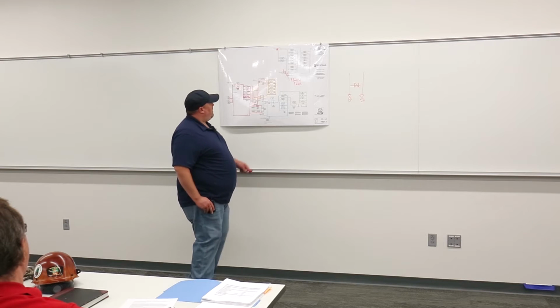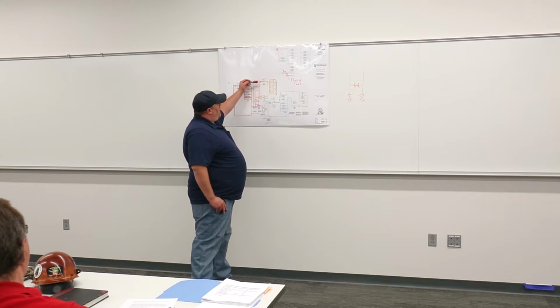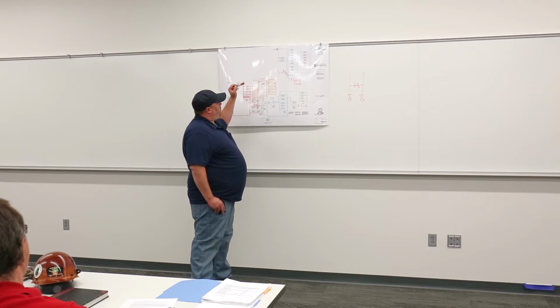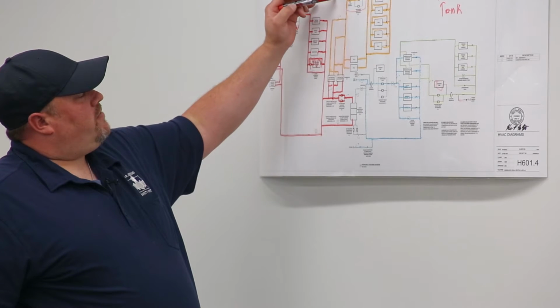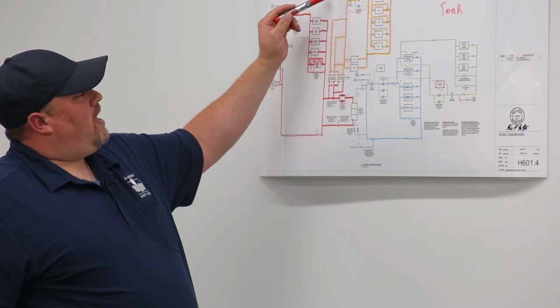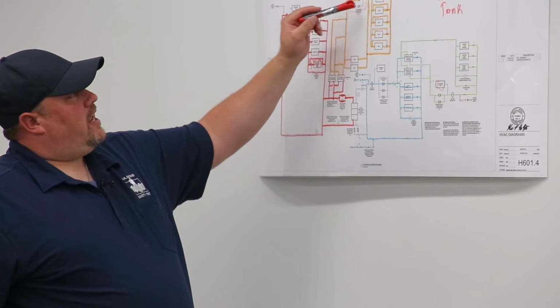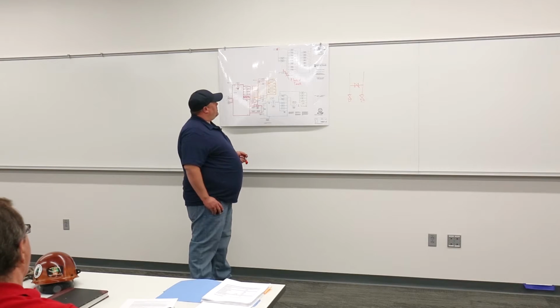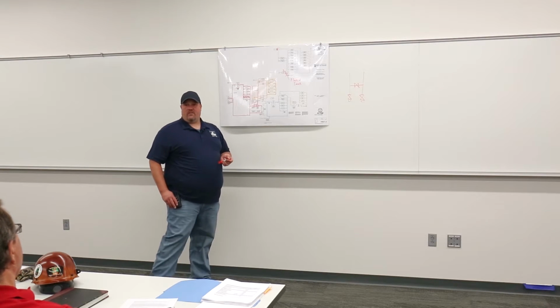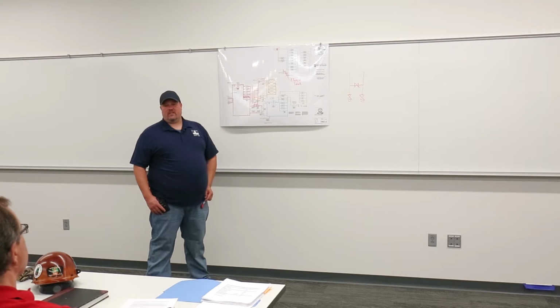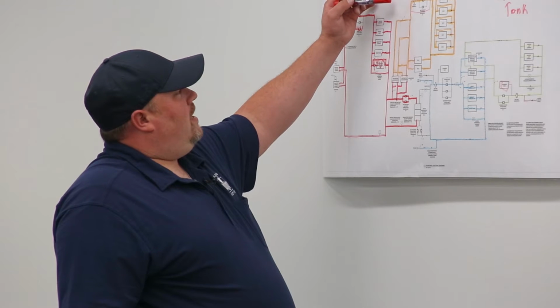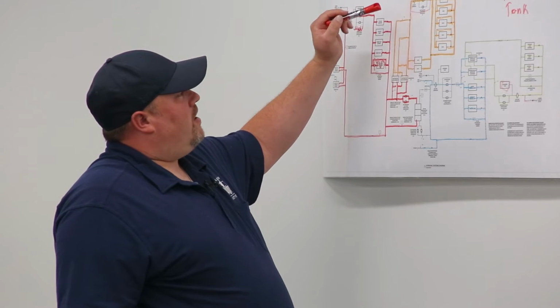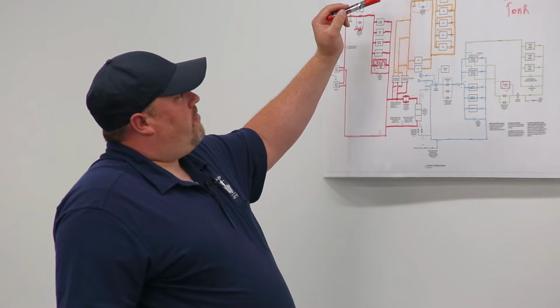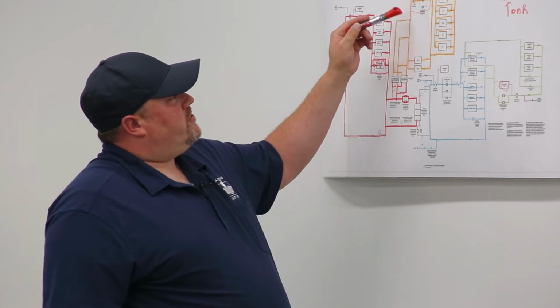The glycol feed system actually has an air and dirt separator that is going to require a blowdown once a month for the first year, the same as all the rest of them located in the building. In that event, you would have to monitor the fill of the glycol and possibly add to the tank in the periodic discharge of the air and dirt separator. It'd probably be a good thing to just hold on to. Every time they do that, it's going to be dirty. They're not going to be able to put it back in. We will be leaving, with the discharge of the air and dirt separator, 2 totes of 30% glycol mix up there for servicing and maintenance purposes.